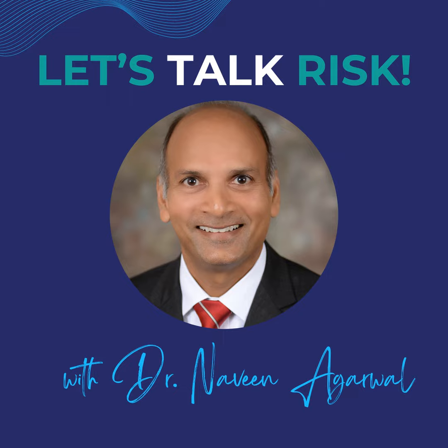Recently, I did a case study on Apple's hearing aid function de novo. And you are absolutely right. They were required to do a human factors study. In fact, more than one. And the special controls do require human factors.